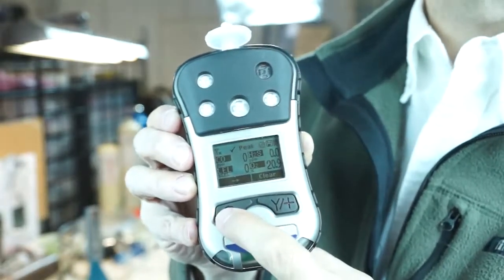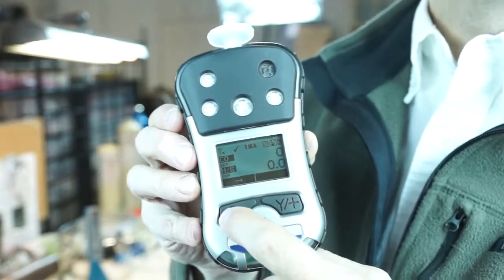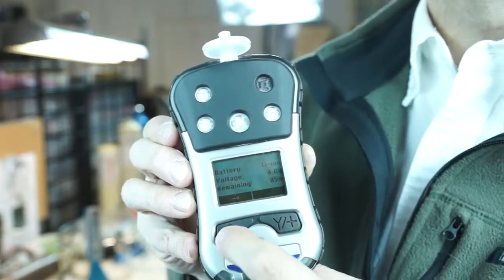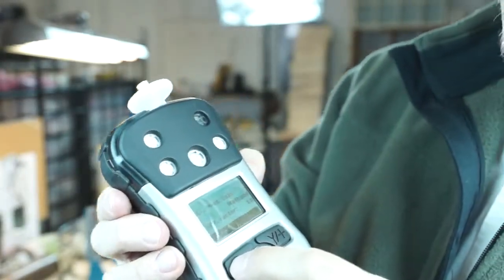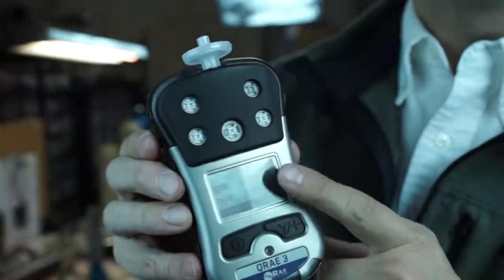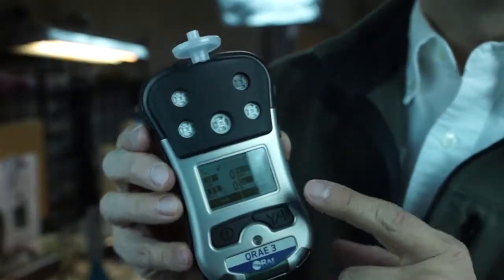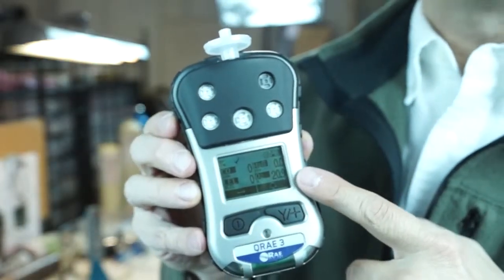By hitting the mode key, you'll see peaks, time-weighted averages, minimums, and STELs — pretty much everything you're familiar with from RAE Systems units as you scroll through. Battery, runtime, and correction factors are also accessible. There are 50-some correction factors internally on the LEL, so if you're working with something other than methane gas, we can set that correction factor accordingly.